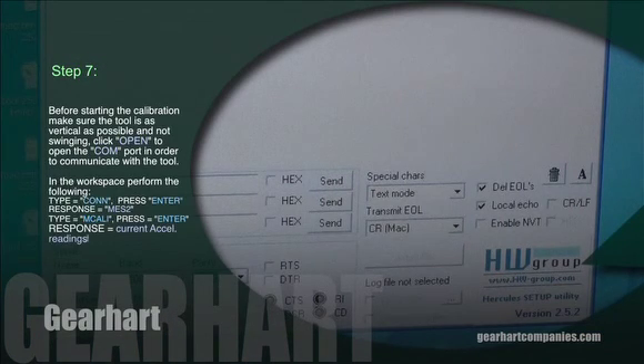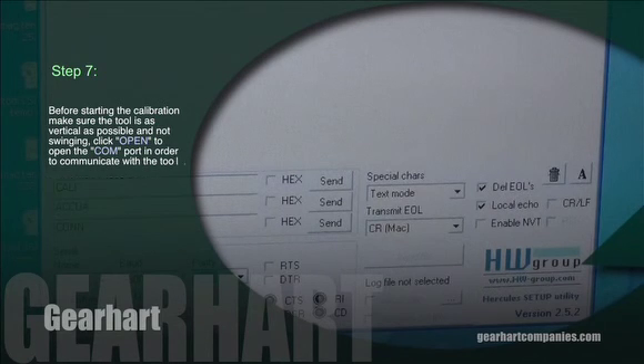Step 7. Before starting the calibration, make sure the tool is as vertical as possible and not swinging. Click Open to open the COM port in order to communicate with the tool. In the workspace, perform the following. Type CONN, press Enter, getting response MES2, then type MCALI, press Enter. Response will be current accel readings for the X, Y, and Z.